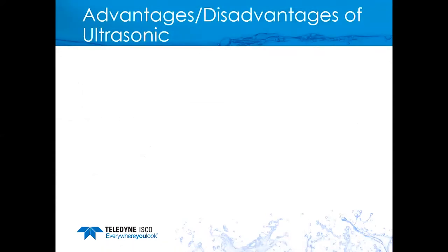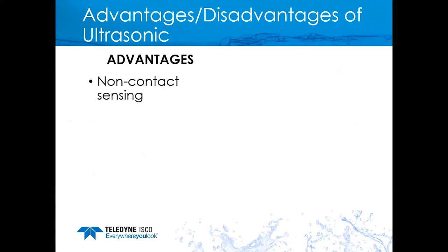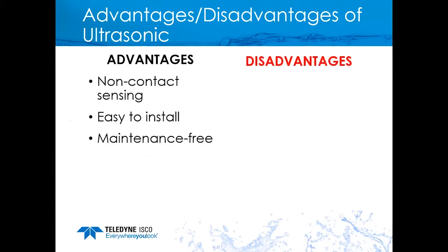Advantages of an ultrasonic sensor: it's a non-contact sensor mounted above the flow stream, making it easier and safer to install. It's maintenance-free because it's above the flow stream — no worry about cleaning debris or rags hanging up on it. Disadvantages include the deadband; depending on your application, you may not have enough clearance above the flow stream. The beam angle can also be a problem in narrow channels, where the beam may hit side walls and produce false echoes.